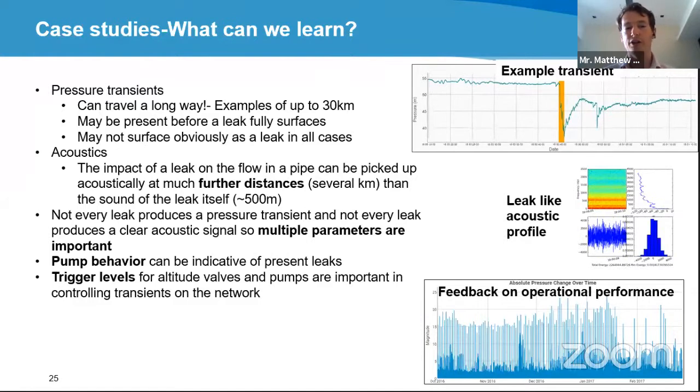We've also found with the acoustics that typically with hydrophones, the expectation is that they can pick up leaks within a distance of around 500 meters. What we find with this type of system is that leaks of certain sizes can generate additional flow on the pipeline. And the sound of this flow in the pipeline through fittings can be picked up at a much larger distance. So I'll show you an example of this a little later on.